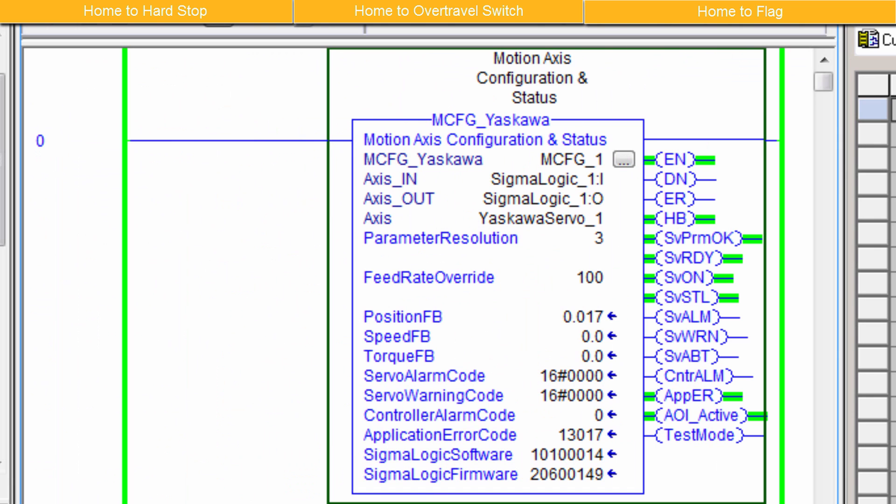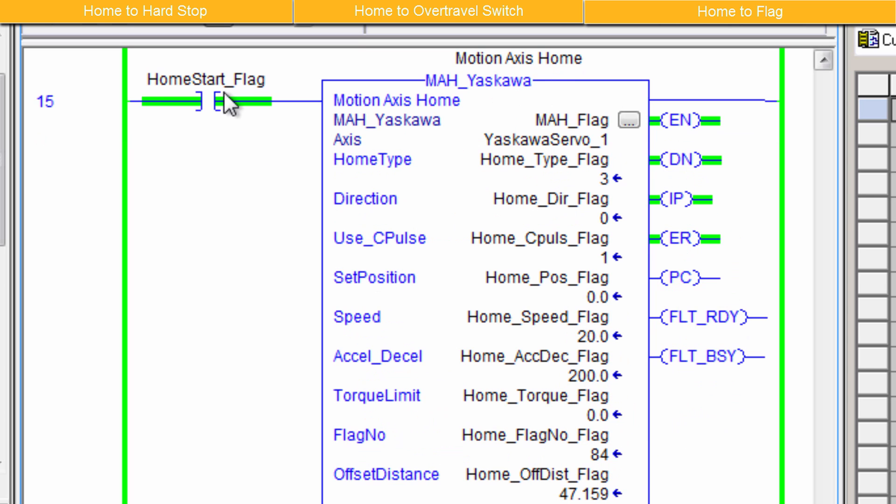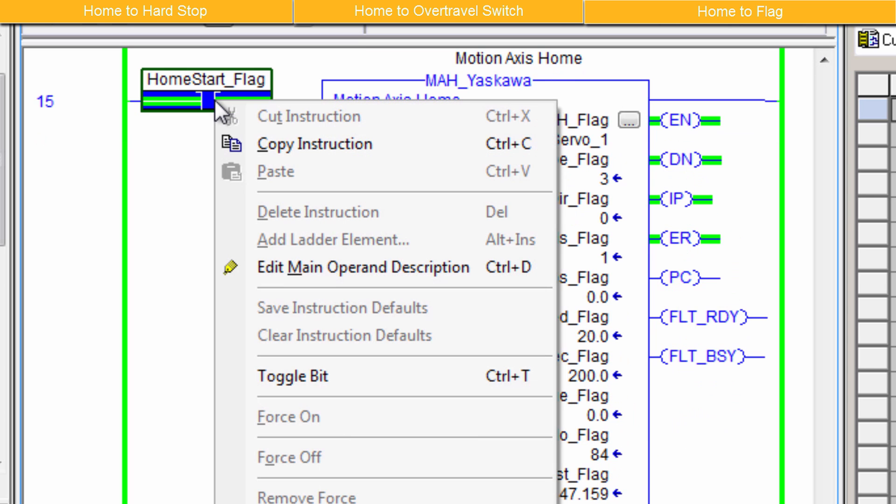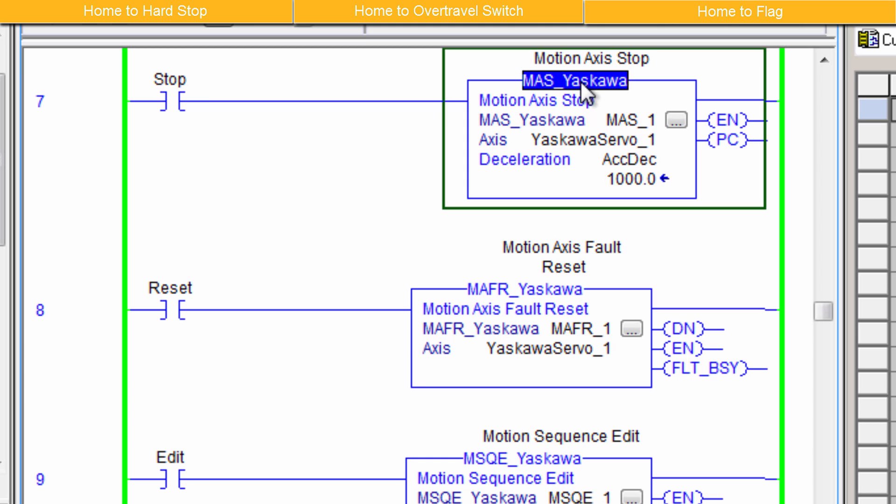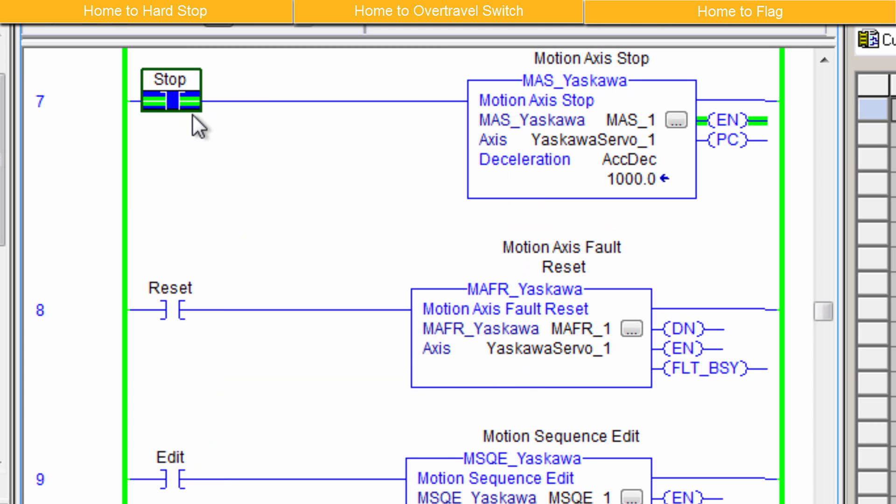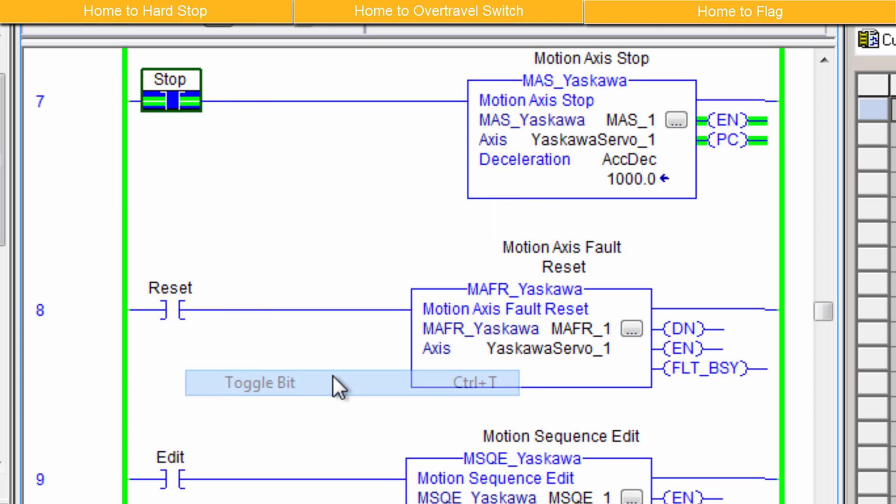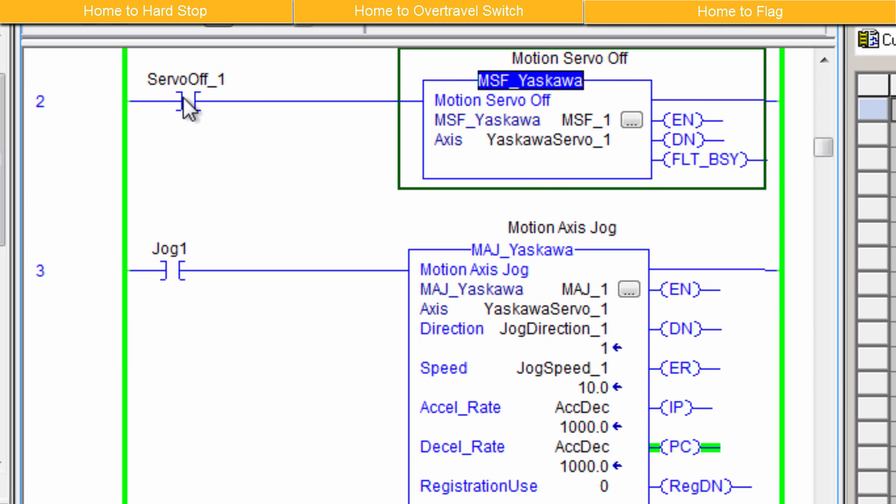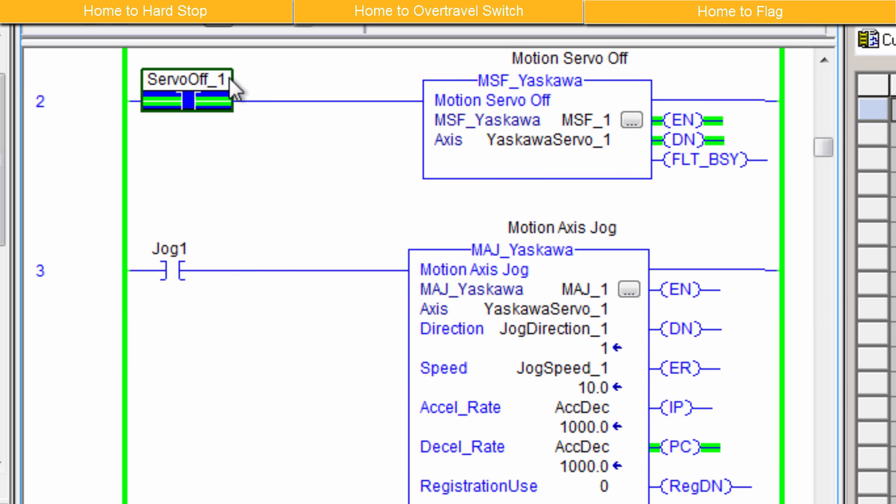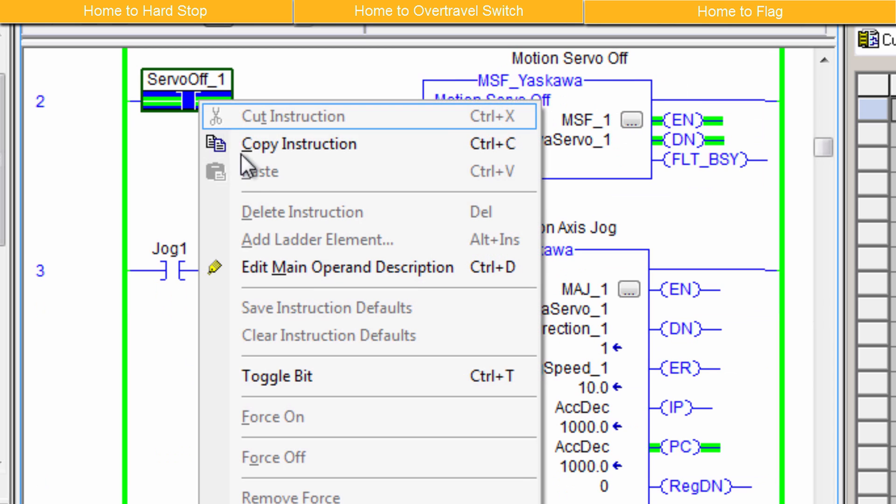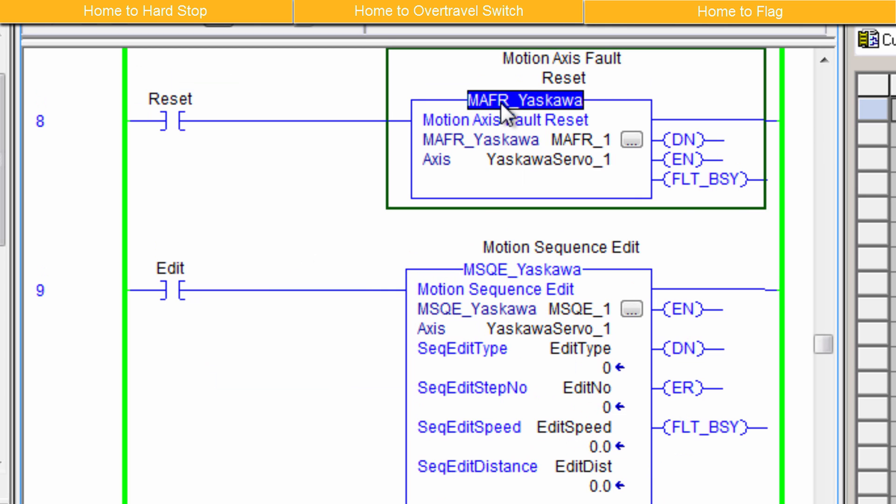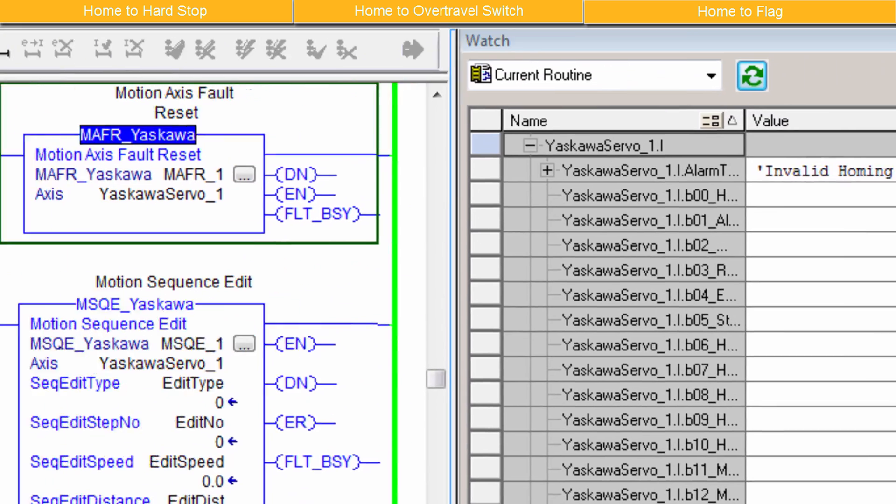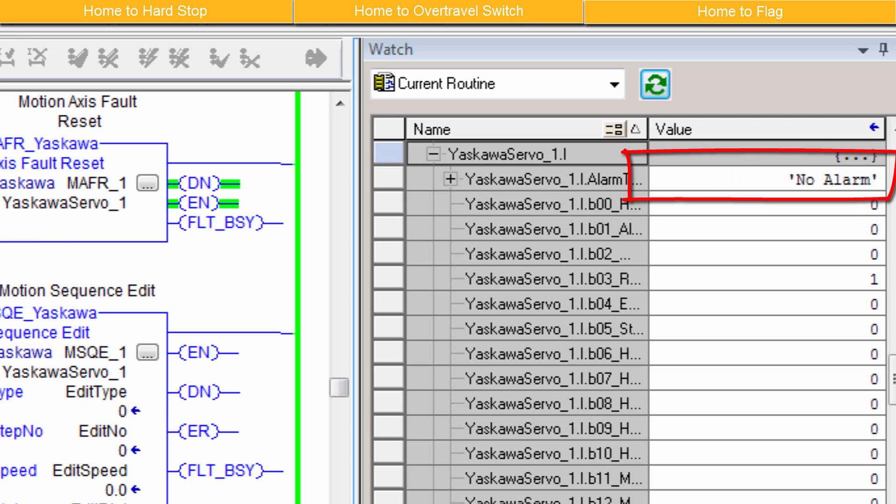To recover from any fault, the following four steps are to be executed in your code. First, release all active AOIs. MCFG does indicate if there is an AOI active. Second, toggle MAS to stop and abort all motion. Third, toggle MSF to ensure the servo is off. And fourth, toggle MAFR to reset all faults.